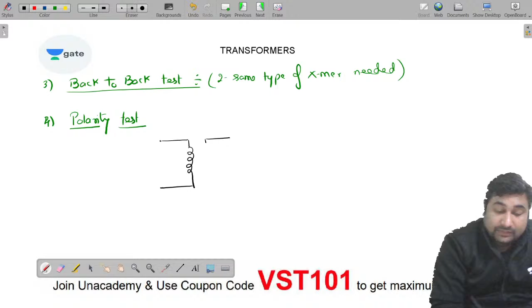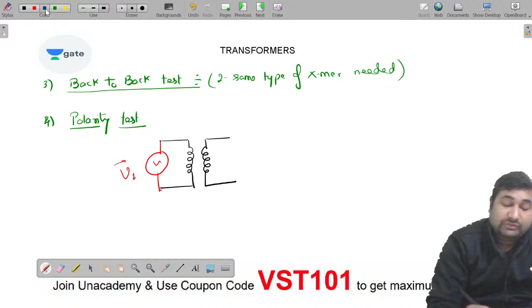In order to perform the polarity test, we go in this way and find the polarities of the transformer. You have to connect a portable voltage source here, say V1 — a low voltage source definitely, because during testing we don't want core losses. So generally we use a low voltage source while testing polarity.